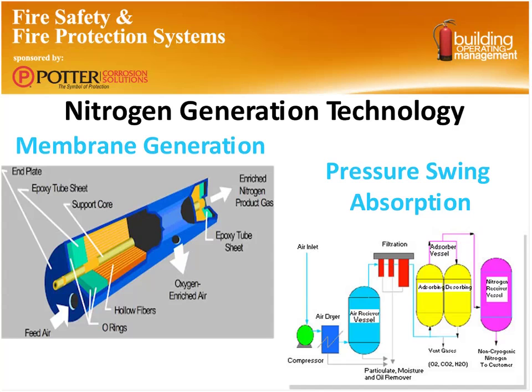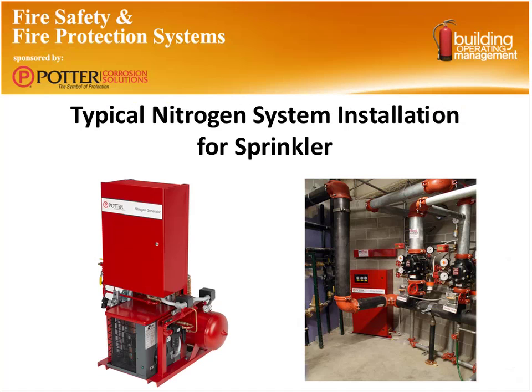The other one is a pressure swing absorption system. Those are a little more extensive systems and haven't been used as much in the fire protection industry. So these are typical generators. This one over on the left is a nice small self-contained unit. You can see the air dryer down here, the compressor and tank, and up here are the other nitrogen controls. This unit is by our sponsor, Potter. There are several other companies that make these types of units for the fire protection industry. And over here, this is a larger system with multiple pre-action risers. This one can be used to protect multiple risers within a facility and give you that corrosion protection and not use the traditional compressed air.